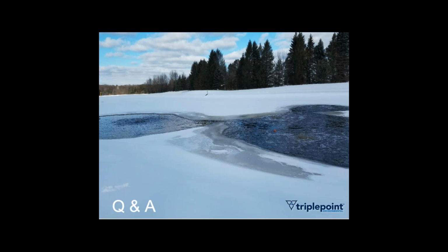Would there be any benefit to installing makeshift scum or sludge pumps to recycle wastewater from the second or third cell to the primary, especially if you have a deeper primary? Then it may be cheaper to just desludge the primary, and anaerobic degradation of organics may increase. So recirculation in general for any lagoon system is always a good idea. It does help improve treatment. We've seen it help improve treatment up to 30%.